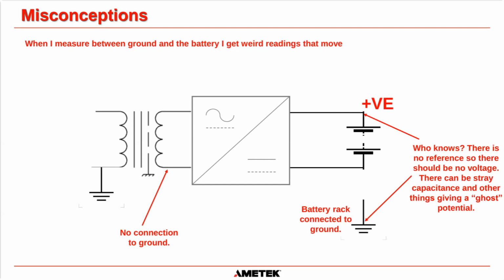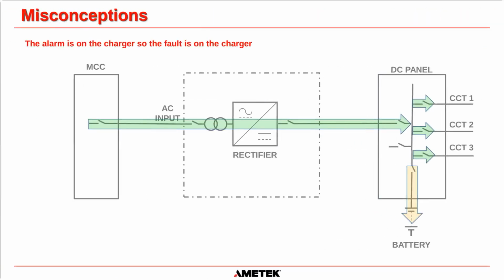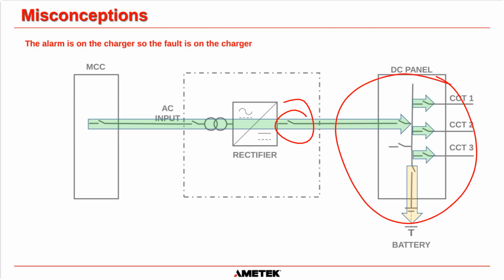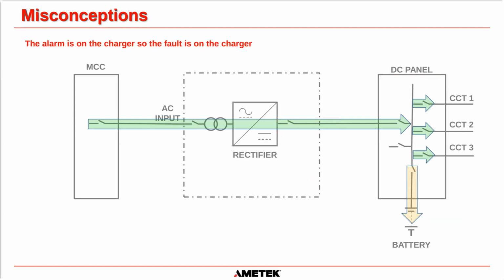No, it's not. It's usually, I would say 95% of the time, maybe even 99% of the time, it is always the load circuits that are causing a ground fault. Okay. So it's not going to be in your charger most of the time, but it's very easy to find that out. Just open that breaker. And if the alarm goes away, that means the ground fault is out here. If the alarm stays with this breaker open, then you have just confirmed, yes, it is in the charger. That is very, very rare.